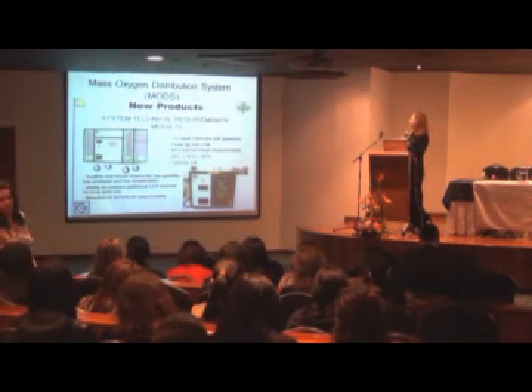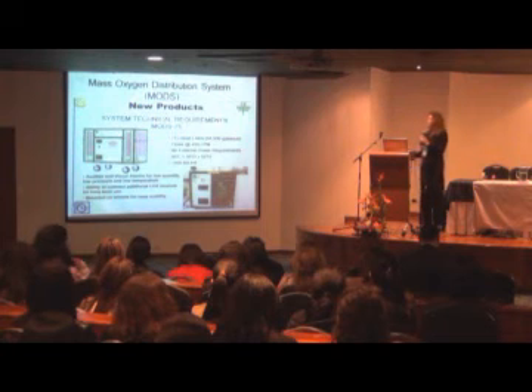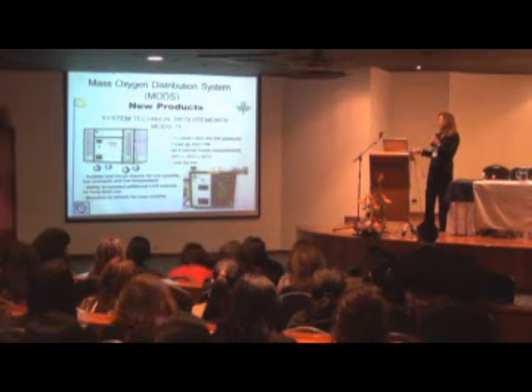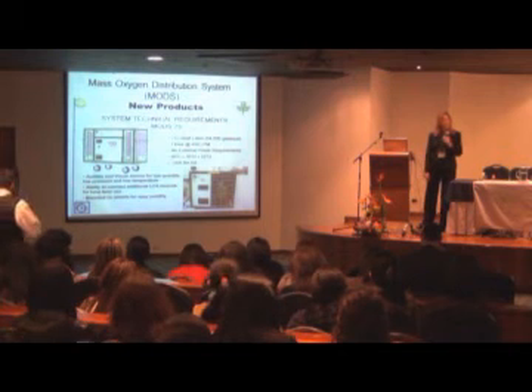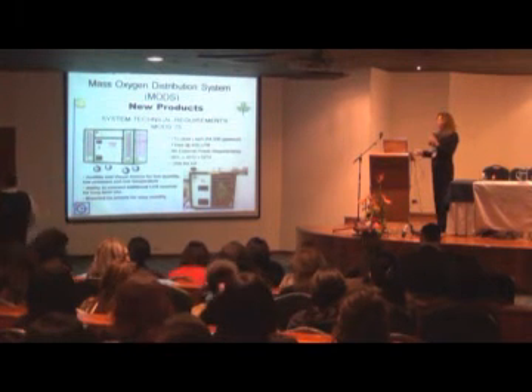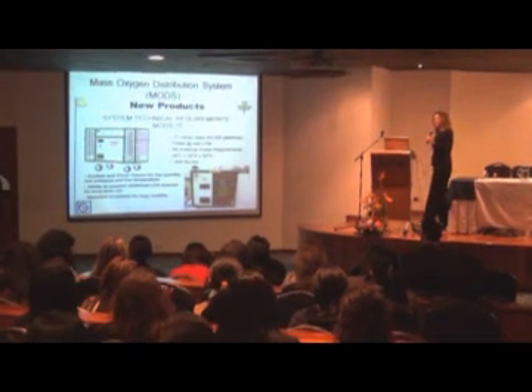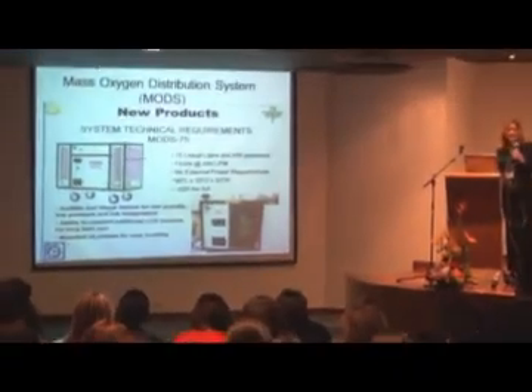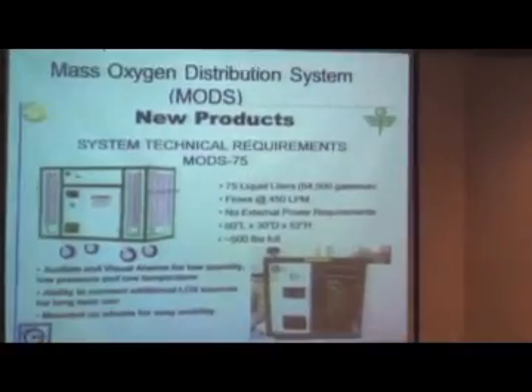Another product that's out here is called the Mass Oxygen Distribution System, or the MOD system. There is a 75-liter liquid oxygen system on board that they can keep in tanks. They can keep full with liquid oxygen. 75 liters of liquid oxygen is the same as 14 H tanks. Much easier to push this around than to carry those 14 H tanks around. No external power needed. From the top of the machine here, it will produce 450 liters per minute. It has the capability of connecting to up to 70 patients at one time with different flow needs, whether it be a ventilator, a nasal cannula, or any type of oxygen mask.